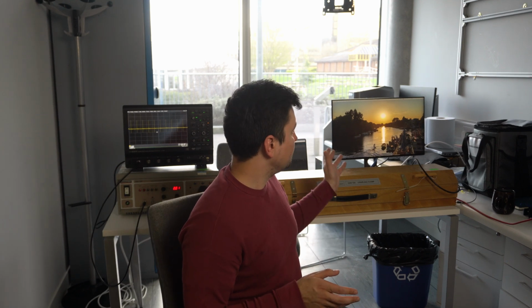I can elaborate a little bit more on the performance criteria. So performance criteria A is obviously no change in the state or the functionality of the device whatsoever, whereas performance criteria B is exactly what we're seeing here: there is some change, however, it doesn't affect the main function of the device as it continues to work. It doesn't restart itself.